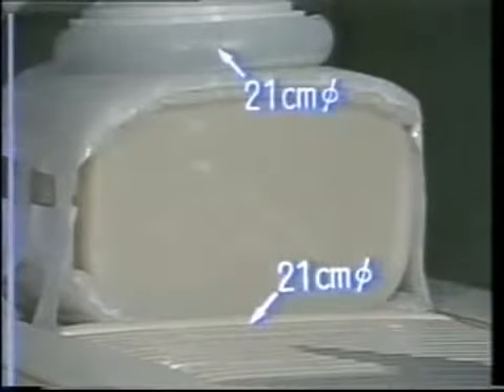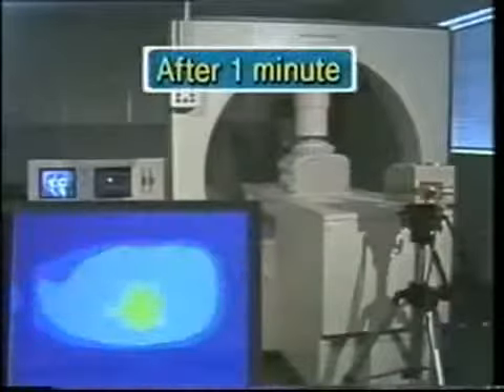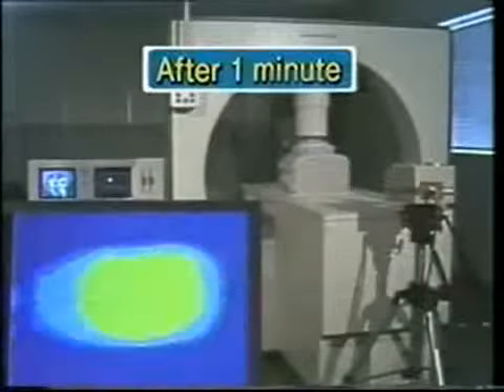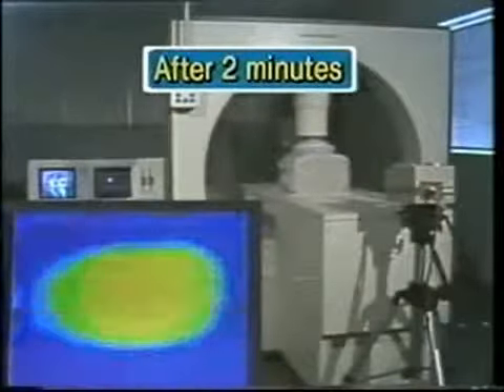For concentrated heating of a deep area 12 to 13 centimeters under the surface, 2 electrodes 21 centimeters in diameter are used. Here we can see well how the central area is heated. The central area is heated to 43 degrees centigrade approximately 3 minutes after heating is begun.